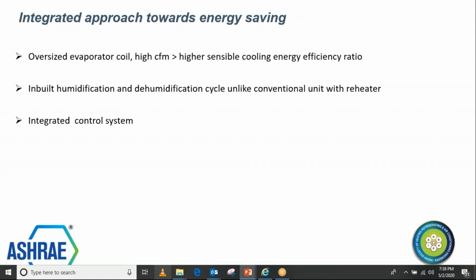So it may happen that you see the RH level is lower, but at the same time different temperature levels. The unit will decide that it may not have to run the humidification to raise the humidity level; just through the control of the unit, it will be able to achieve this level of humidification. The same is applicable for dehumidification also. So this avoids overheating and overcooling, and also over-dehumidification and humidification. These are the operation level savings achieved when we compare both systems like to like.